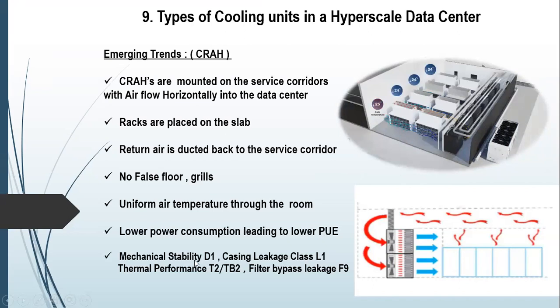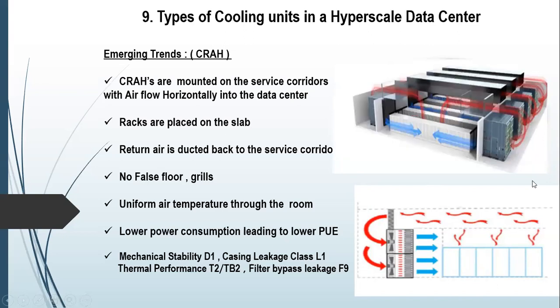You can find the terminologies of stability and the casing leakage, L1, thermal performance rating is at around TB2, T2, depending upon the type of fan wall units. But the criteria or the parameters of AHU also comes into picture. So here you can see the temperatures are maintained with the help of the temperature sensor and the EC fan. Then you maintain the temperature at 24, which is well within the bracket of the ASHRAE norms. So this is just a schematic diagram of the fan wall units.